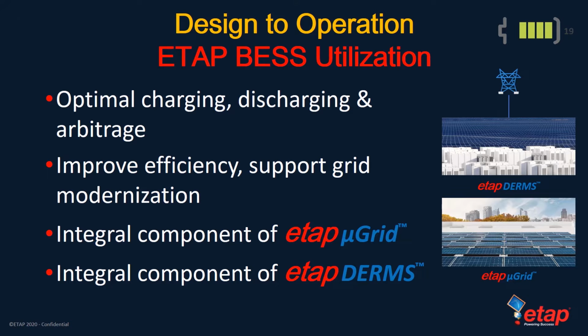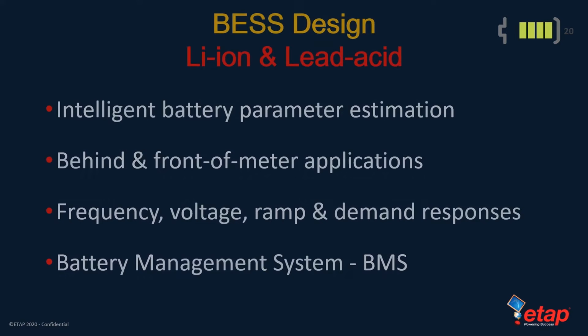The BESS implementation in ETAP is an integral component of ETAP microgrid controller, as well as an integral component of ETAP DERMS, or Distributed Energy Resource Management Systems. We can use intelligent battery parameter estimation inside the ETAP BESS implementation. It can be used for behind and front of the meter applications. And you can use the BESS modeling and simulation in ETAP for frequency, voltage, ramp, and other demand response simulations. And finally, it also includes the implementation of battery management system, or BMS.